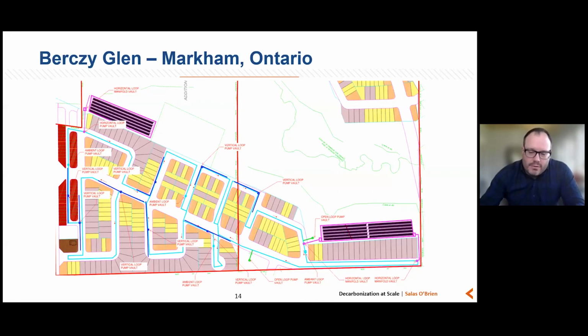And then switching gears very drastically, this is outside of Toronto. This is single family or very low rise residential development. I put this in here only to suggest that there are lots of ground source heat pump models, and ground source heat pumps with air source heat pumps integrated with them, that are being looked at, and there are test cases and real developments happening throughout North America in cold climates that look at using these technologies as efficiently as possible. And I know National Grid and Orange and Rockland are two utilities on the East Coast that are doing pilot programs for this as well. And this is a single pipe ambient system through about a 300 home development outside of Toronto that uses ground source heat pumps and vertical heat exchangers integrated in the public right of way.